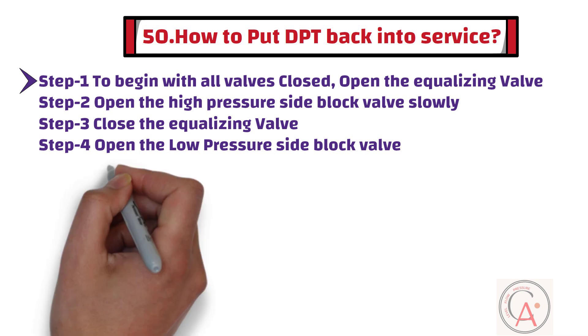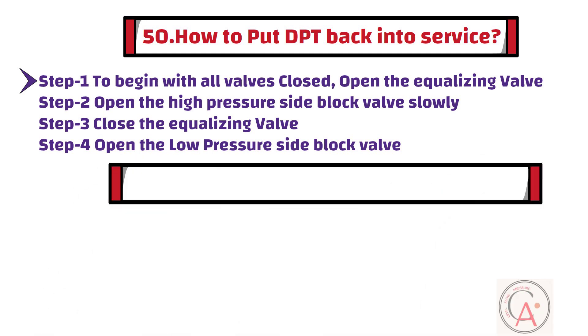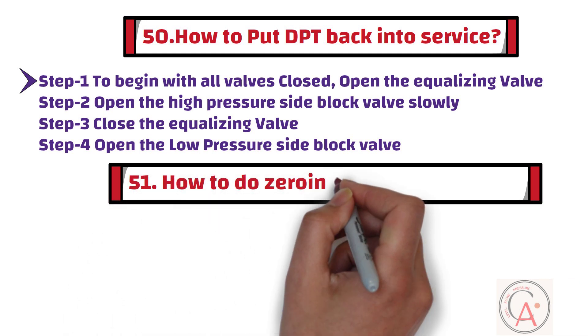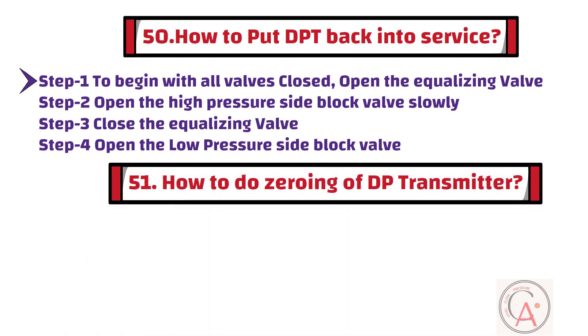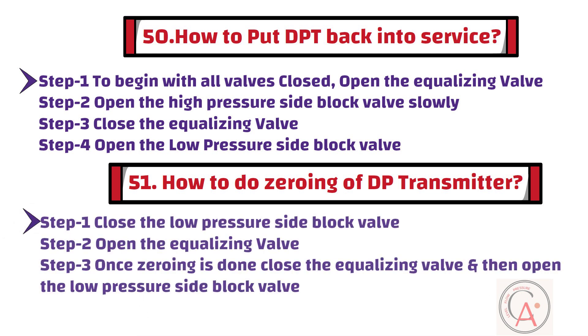Question 51: How to do zeroing of a DP transmitter? To do zeroing of the transmitter, first close the low pressure side block valve. Then in step 2, open the equalizing valve. Finally, once zeroing is done, close the equalizing valve and open the low pressure side block valve.